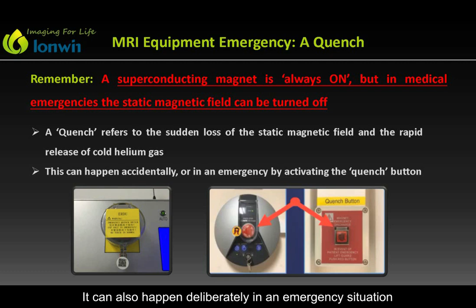During a quench, the liquid helium rapidly boils off and becomes a gas. Helium gas vents outside of the building via the quench pipe, which is usually at the top of the scanner. You should beware, however, if the quench pipe fails, there may be a buildup of gas and pressure in the MRI scanner room. Risks of a faulty quench pipe during a quench include asphyxiation due to a decrease in the available oxygen in the room, and frostbite due to the extremely cold temperatures of helium. Another important consideration is the damage to the MRI system and associated costs of repair, as it can often take some weeks or even months to repair an MRI system after a quench.